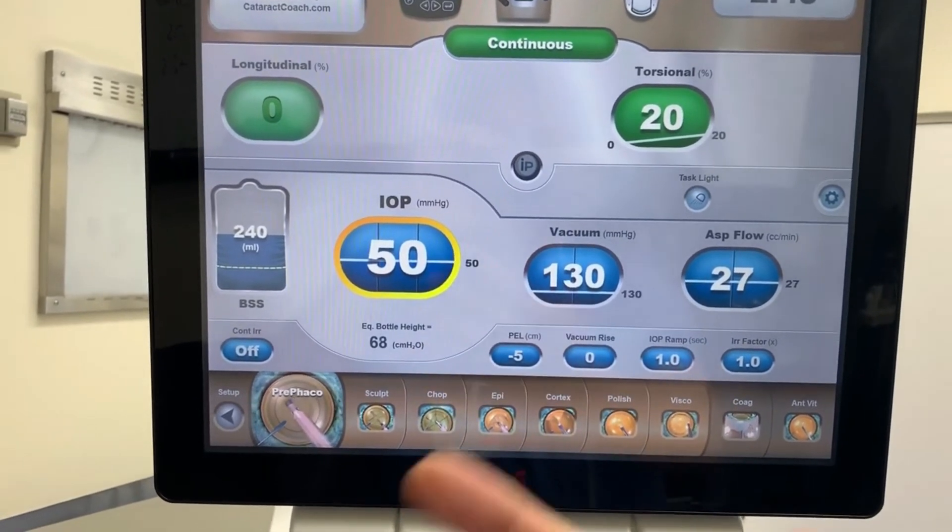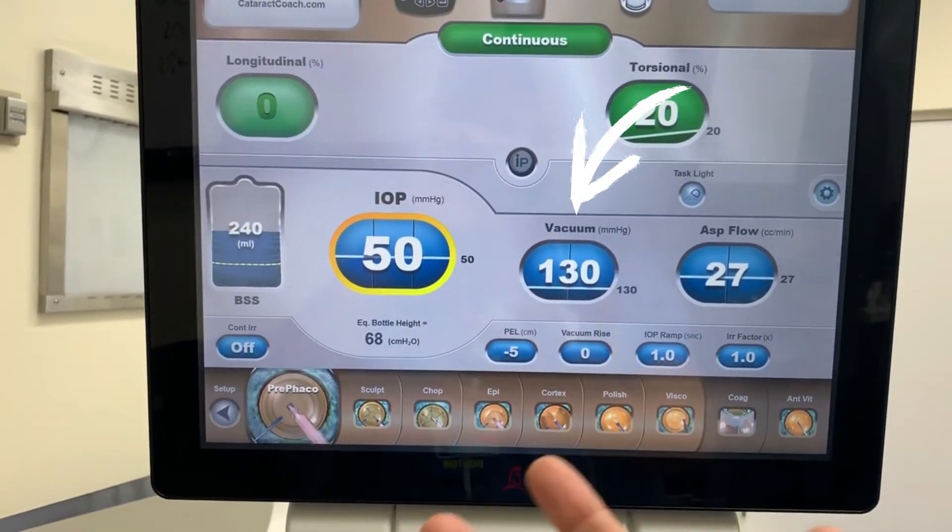Second control is vacuum. The difference in fluid pressure among two points. Negative pressure measured in millimeters of mercury, mmHg. Vacuum determines how well, once occluded on the phaco tip, nuclear material will be held to the tip, holding power.